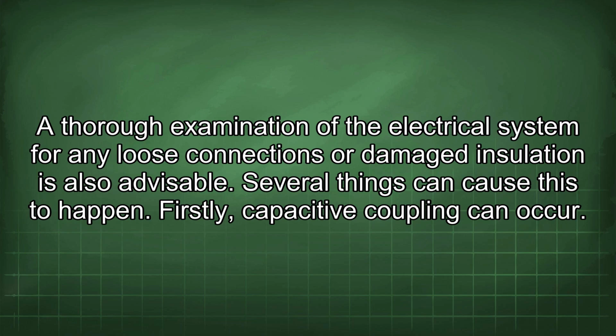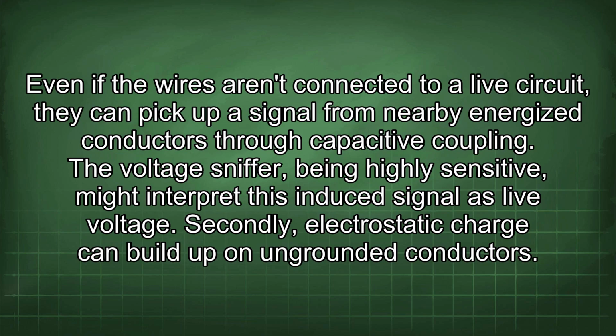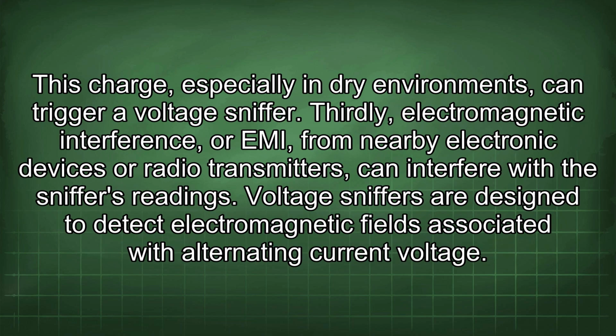Several things can cause this to happen. Firstly, capacitive coupling can occur. Even if the wires aren't connected to a live circuit, they can pick up a signal from nearby energized conductors through capacitive coupling. The voltage sniffer, being highly sensitive, might interpret this induced signal as live voltage. Secondly, electrostatic charge can build up on an ungrounded conductor. This charge, especially in dry environments, can trigger a voltage sniffer.